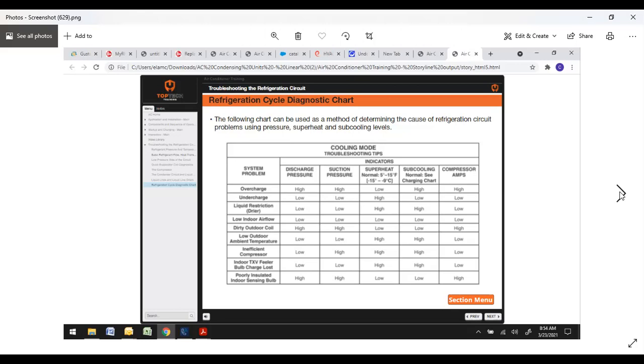If you think, well, I'll just add some refrigerant, get this juiced up a little bit, what happens usually if you have a bad TXV where it's not going to change, it may go up slightly, but your discharge or head pressure is going to jump up higher than it should, but your suction pressure will remain the same or go up about 10 psi and drop back down again. And I'll get into in just a minute how you can exercise your expansion valve to test that.